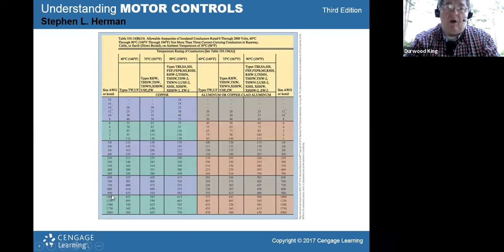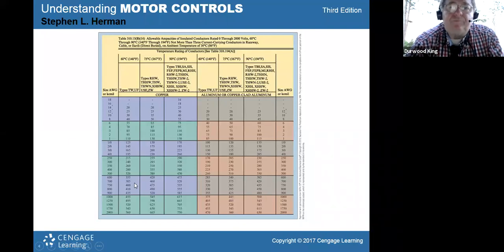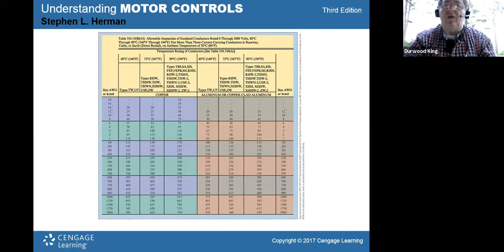So it's a very large conductor. It's very likely that it wouldn't even be a single wire, but multiple wires per phase. I've never seen a motor wired with wire that big. They would actually do parallel conductors equivalent to 900 kcmil. They may get three of these 300s to make a 900, do three 300s per phase, and have them paralleled on large terminal blocks that are jumpered together. I've seen pictures of things like that, with multiple cables or wires per phase in a system. So that's more than likely what you would see there.